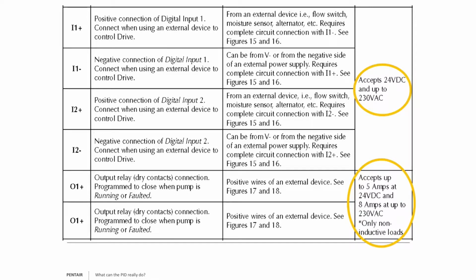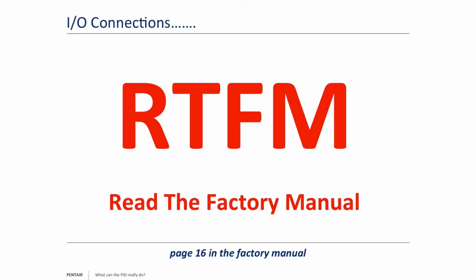If you are to try to start a pump with this, what we recommend is you use a mag relay. So you would have 115 or 230 volt coming into the circuit. You give it a command to say, when the pump is running, I want this output to close. So it starts the unit, the output relay closes and passes voltage down to a mag relay, which then snaps shut and closes the pump start relay and energizes the pump. So there, like I say, the inductive load is taken off of our box because we have a pump start relay. Do not try to use our unit as a pump start relay, though, directly.